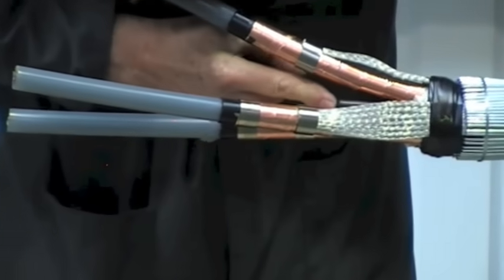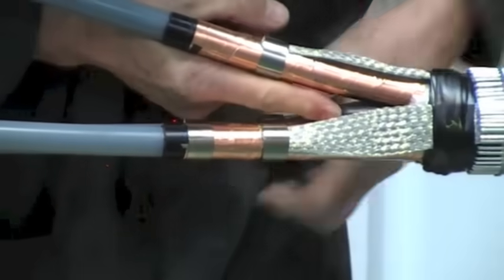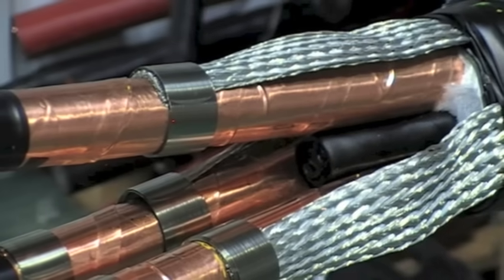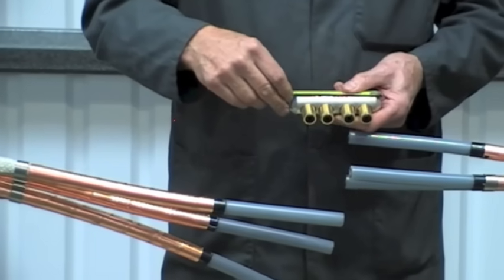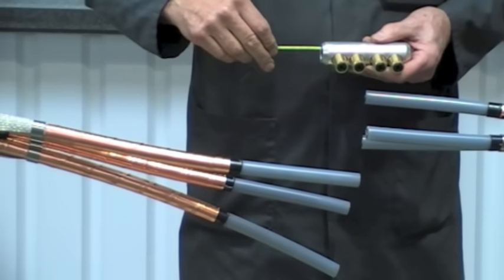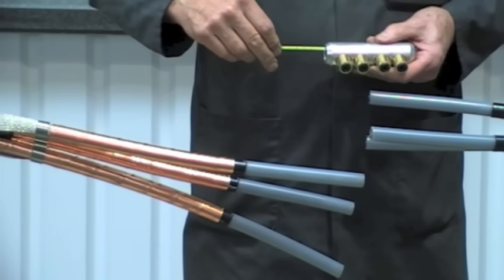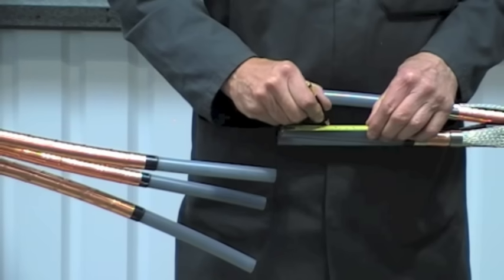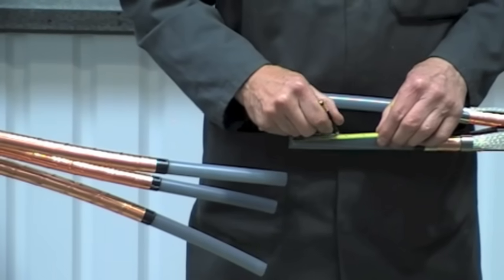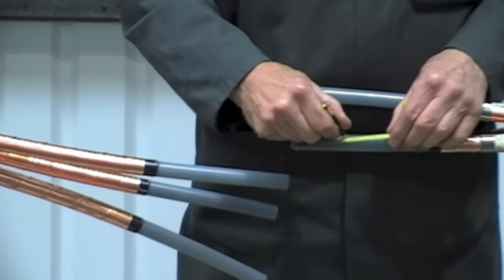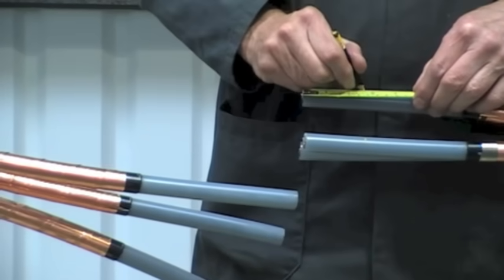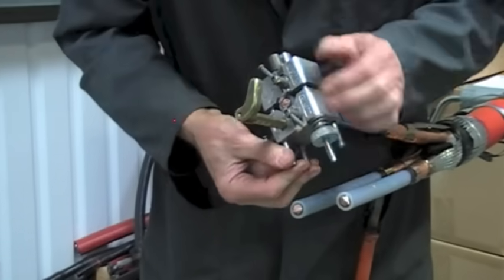Now we're fitting a mastic crutch wedge to help prevent moisture that may be existent in the cable. We're now going to fit medium voltage mechanical connectors. The advantage of these is they will suit copper or aluminium conductors and will cover a wide cable range. So mark out the primary insulation to half the length of the connector plus 5mm.